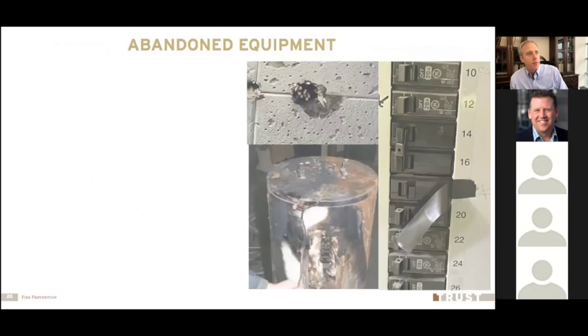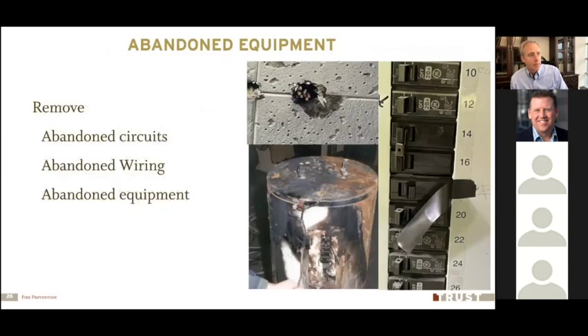Another really common problem that we see is abandoned equipment, and I mentioned before that I was going to bring this up. Sometimes we'll see a circuit breaker in the off position, and we'll just put a piece of tape over it, and that's supposed to tell people not to turn this breaker on. It's not uncommon that we come across these and see the piece of tape hanging there. Over the years the adhesive on that tape goes away and the tape falls off eventually. Sometimes we'll open that panel and the tape has totally fallen off.